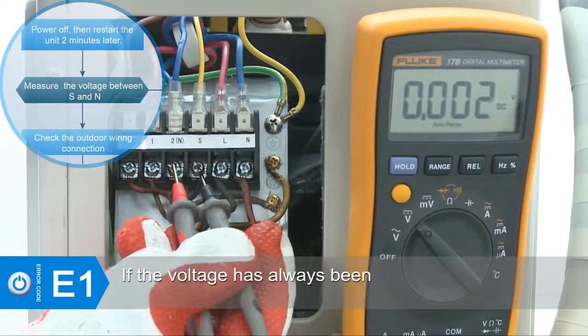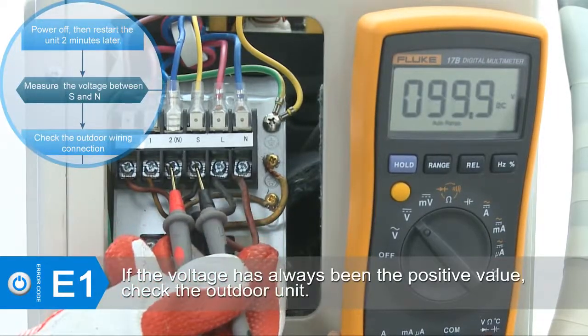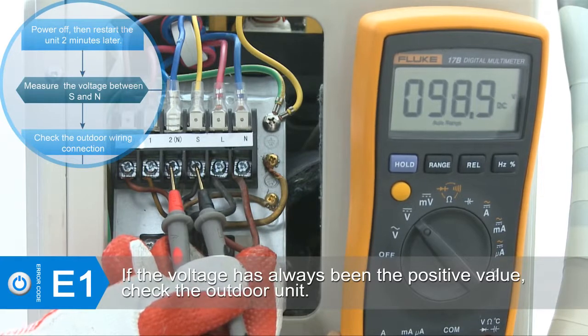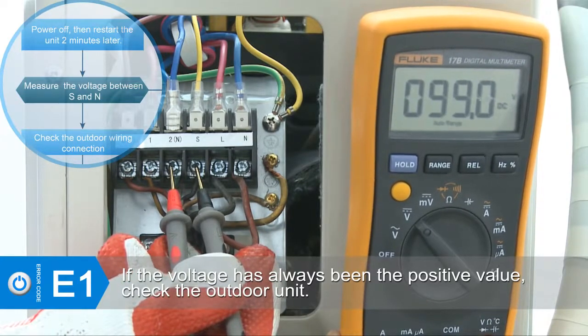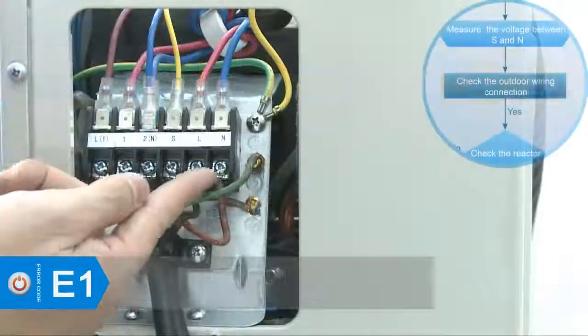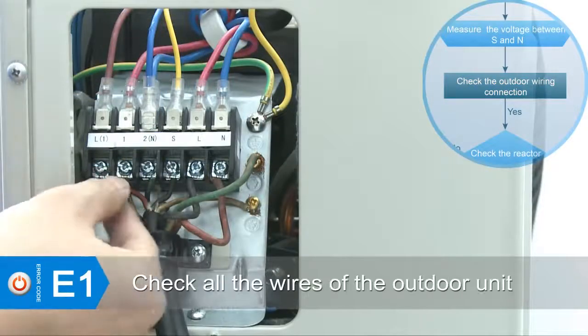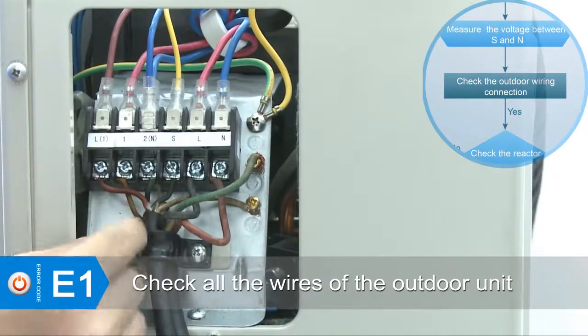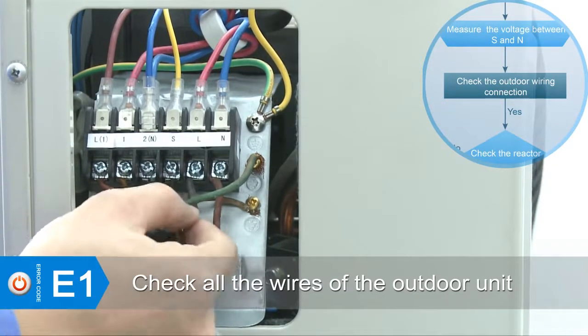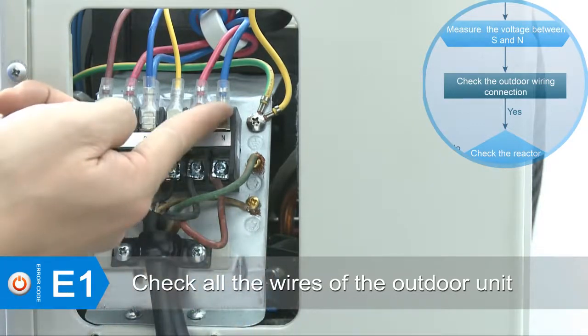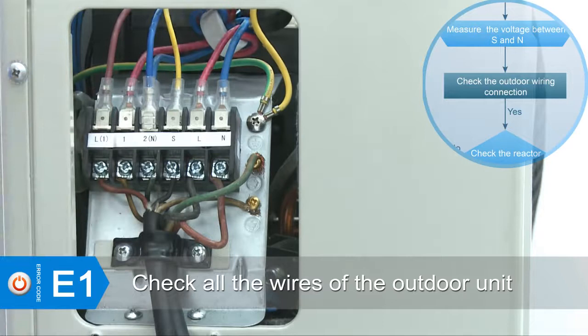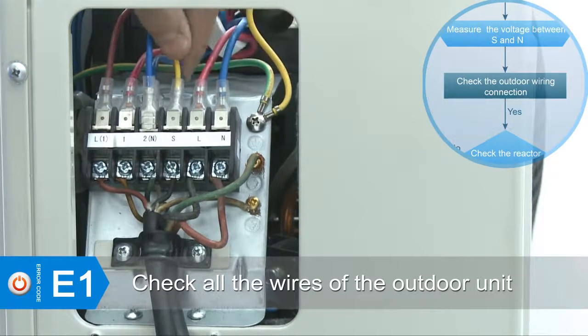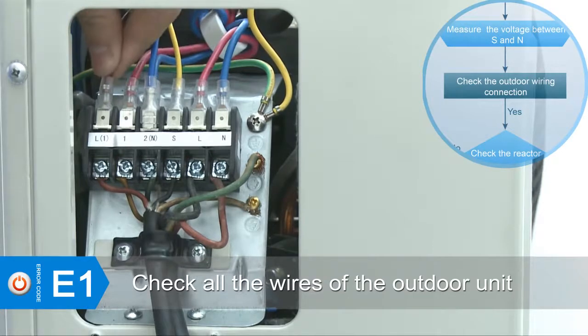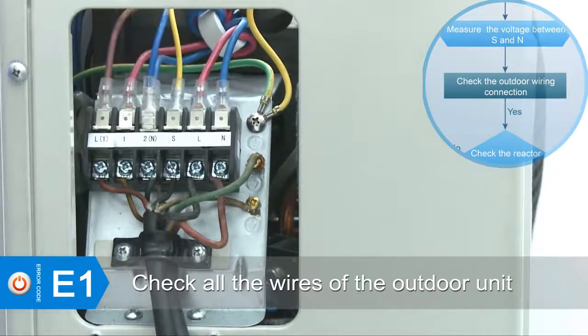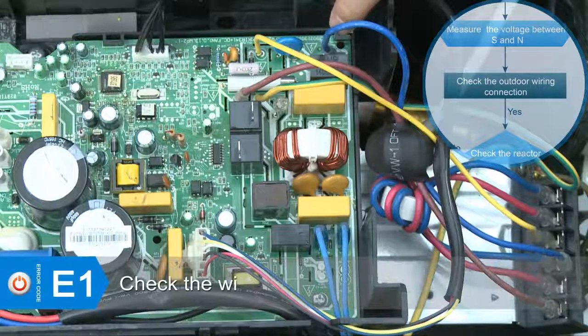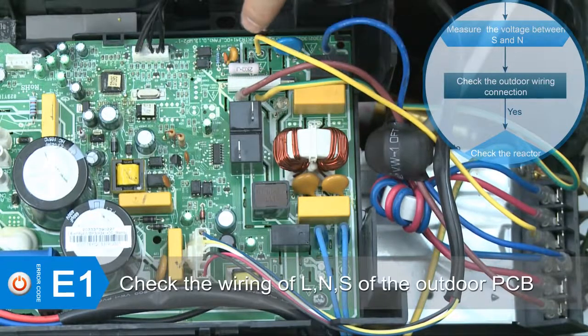If the voltage has always been the positive value, possible malfunction may be occurred on the outdoor unit. Main attention should be paid to the outdoor unit. Check the wiring of the outdoor unit, which includes the power wires and the connecting wires between the indoor and the outdoor unit. Check the wiring of L, N and S of the outdoor PCB.